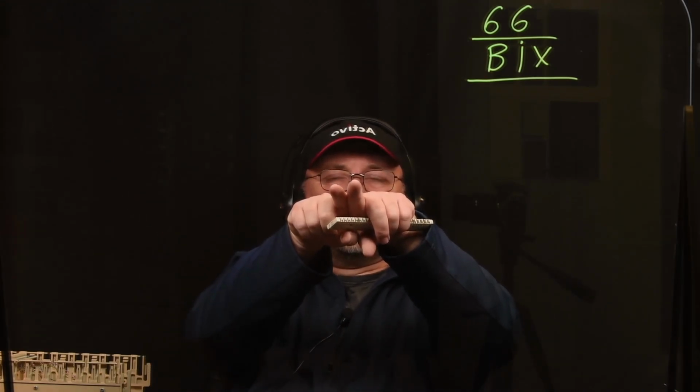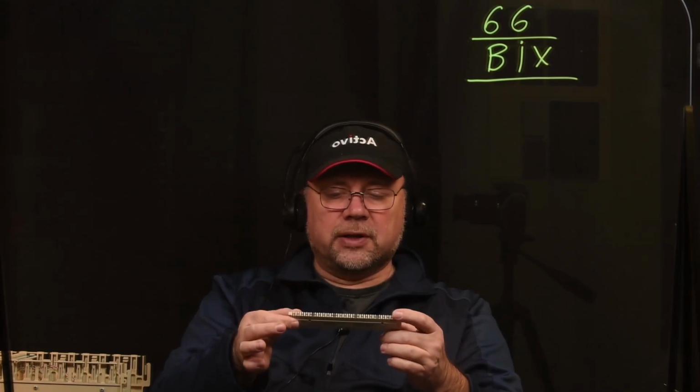So let's say you have an orange pair and a green pair, and you use the solid because both of them are damaged. So there's one good conductor from one pair and there's another good conductor from another, and you can just get these two to create a pair. The problem with that, there's a huge possibility of creating a crosstalk or affecting other pairs, because then you lose the twist. We'll talk about that in the further lecture sessions.